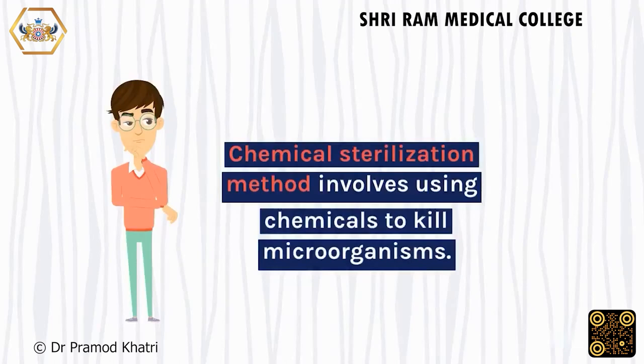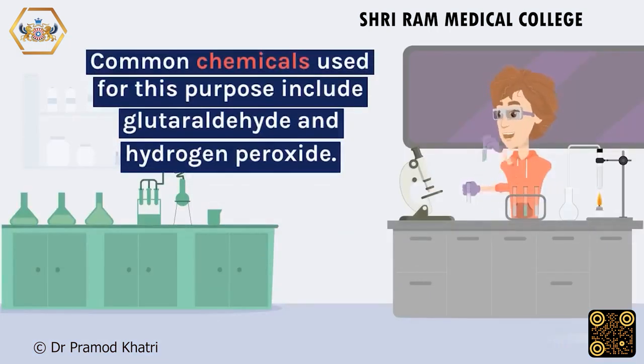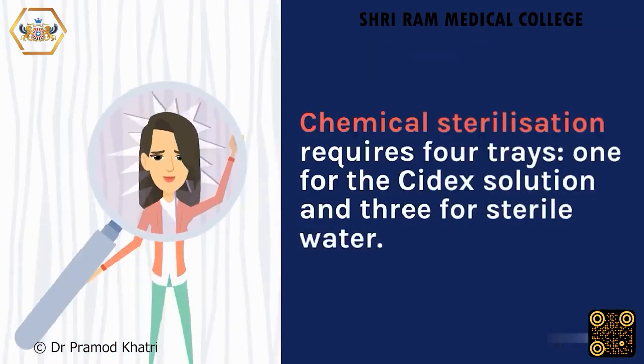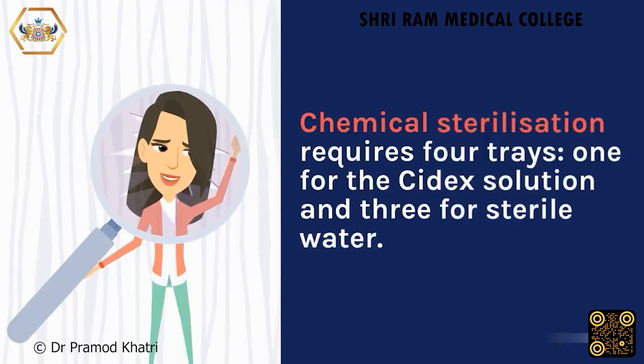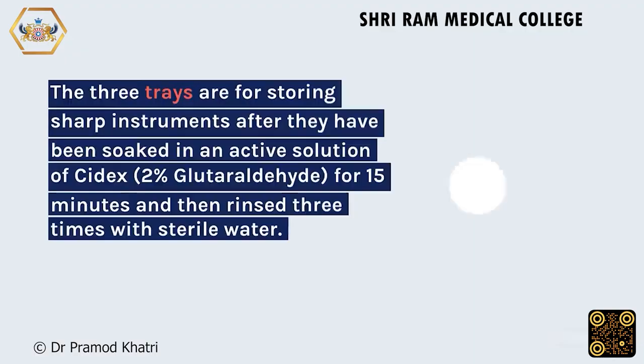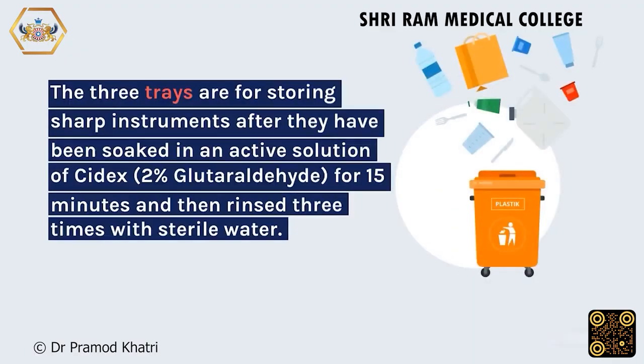Chemical sterilization method involves using chemicals to kill microorganisms. Common chemicals used for this purpose include glutaraldehyde and hydrogen peroxide. Chemical sterilization requires 4 trays, 1 for the Cidex solution and 3 for sterile water. The 3 trays are for storing sharp instruments after they have been soaked in an active solution of Cidex, 2% glutaraldehyde, for 15 minutes and then rinsed 3 times with sterile water.